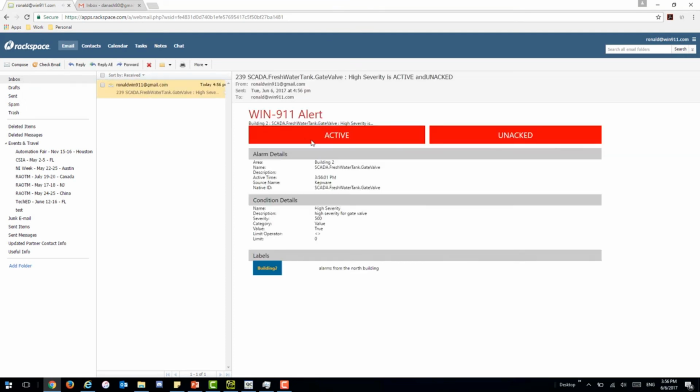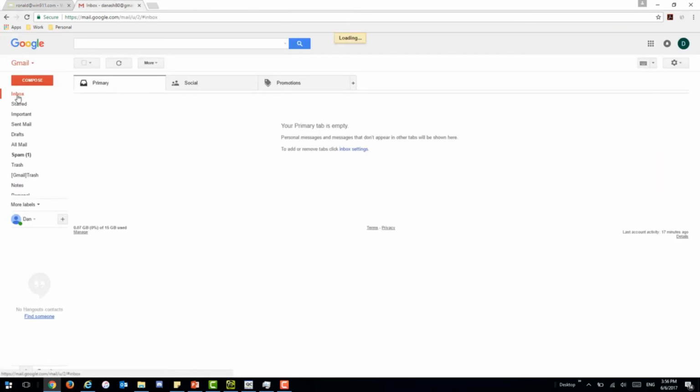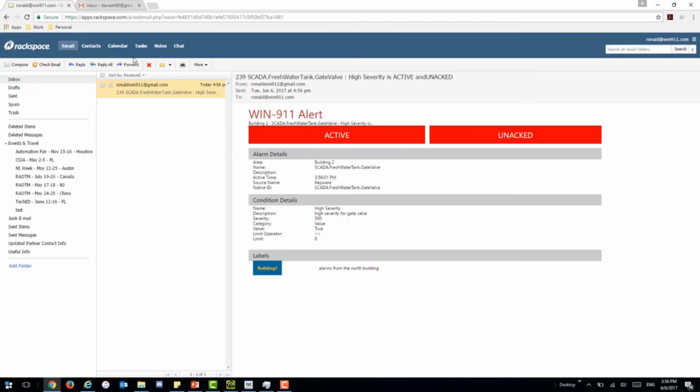And we are expecting, perfect, that this comes through. You can see it's active and unacknowledged. All the information is here. Awesome. Again, let's check Dan, make sure this works exactly as we thought it should. Dan is getting nothing, so only Ronald is being notified.